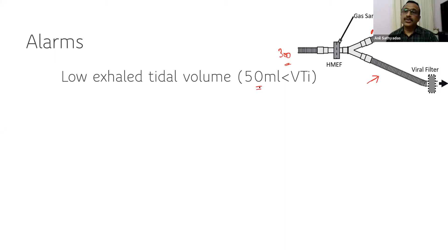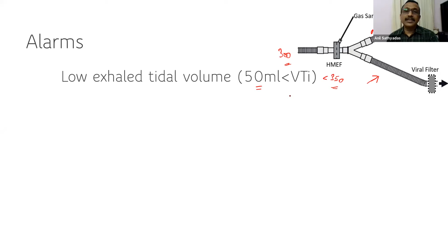So when the exhaled tidal volume is less than 350 ml, an alarm should sound, telling you there is some kind of problem. We have asked the ventilator to give 400 ml, but it is not able to get back more than 350 ml. So there is a leak somewhere. You have to troubleshoot. The pressure alarms are usually kept 10 centimeters above and below the baseline. For high inspiratory pressures, troubleshooting would be a block in the tube, or again a very stiff lung. I hope you remember the first picture we saw: either a stiff lung or a block in the tube. Low pressures signify leaks, a cuff leak or some other kind of leak.